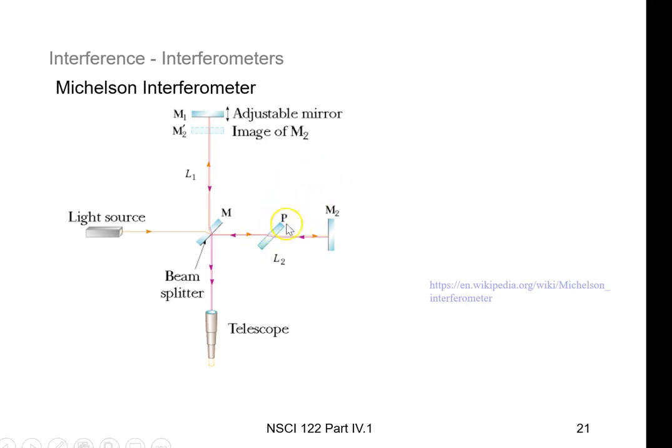But some of them will have this compensator plate. I'll tell you real quickly what it does. See in the beam splitter, to get to this metallized part, the light has to go through this thickness of glass right here, right? Well, the compensator compensates for the fact that beam 2, the one that's in arm 2, only has to go through that piece of glass on the beam splitter once, right?